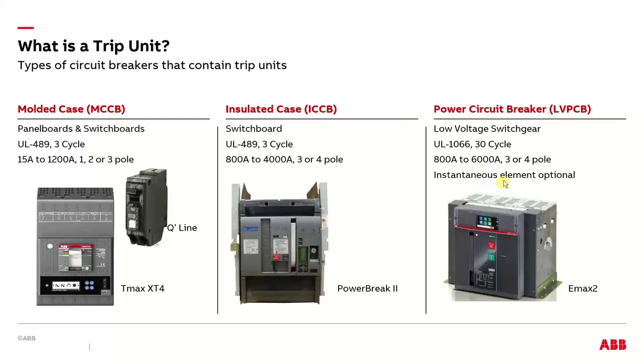These are current ratings. And what makes it interesting is that when you get to the UL1066 devices, you don't need instantaneous protection, and that was one of the questions. When you're in the UL489 listings, you need to have a non-delayed or instantaneous trip, because the actual equipment it's protecting, the bus it's connected to, is only rated for 3 cycles. So if you get that short circuit, you have to come offline without a delay. With power circuit breakers, the bus is rated for 30 cycles, so you can essentially sit there with a high fault current and wait. What you're waiting for, hopefully, is some of your downstream protection to operate. That's what provides you with selectivity in breakers.